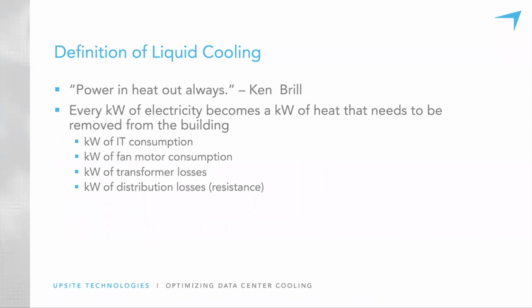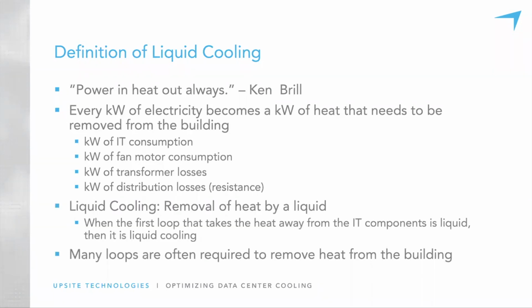Now let's talk about the definition of liquid cooling. This is really important in being able to have informed conversations about liquid cooling. Ken Brill had a saying which was power in, heat out, always. Every kilowatt of electricity that goes into a data center building becomes a kilowatt of heat that needs to be removed from the building. This includes all the IT equipment, of course, all the fan motors, pumps, transformer losses, distribution losses, all of those things consume kilowatts of electricity and turn it into kilowatts of heat that need to be removed in some way. So liquid cooling is when the removal of the heat is done by liquid.